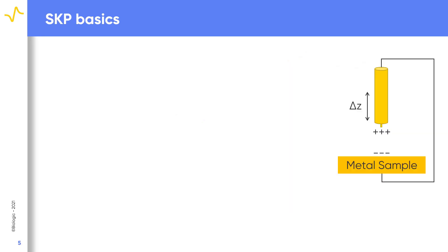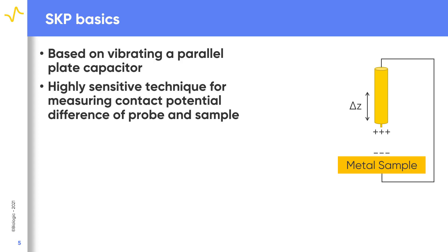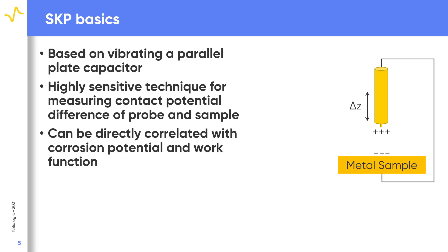Regardless of the signal of interest, the basics of the technique are the same. Scanning Kelvin probe is based on a vibrating parallel plate capacitor. It is used for measuring the contact potential difference between the probe and the sample, providing a highly sensitive measure of the sample surface. The contact potential difference measured in SKP can be directly correlated to the corrosion potential or the work function of the sample.